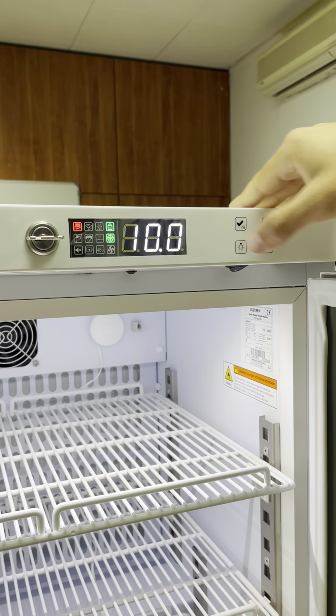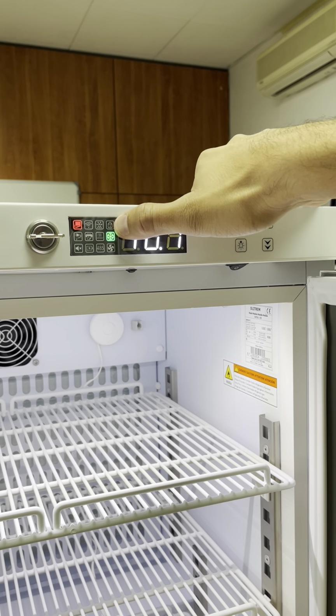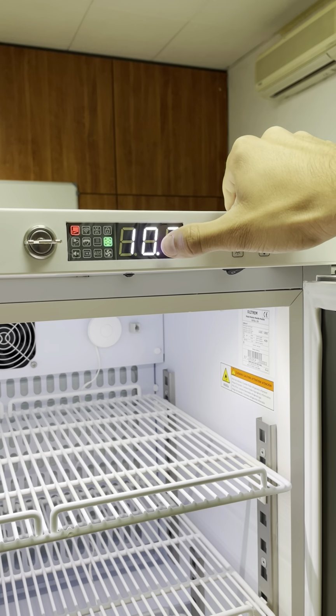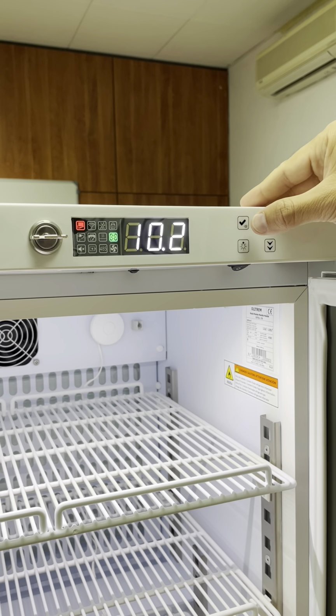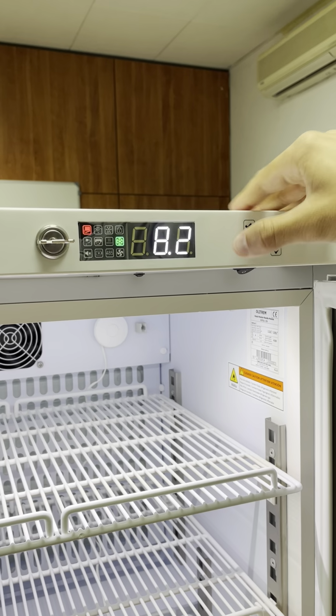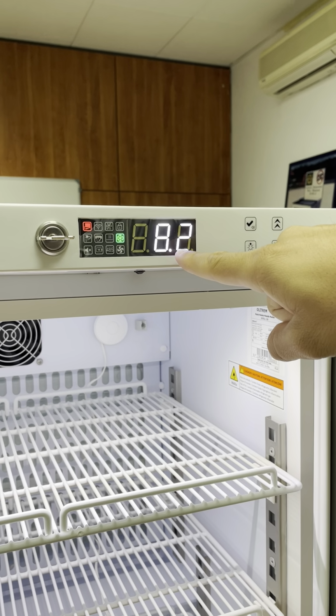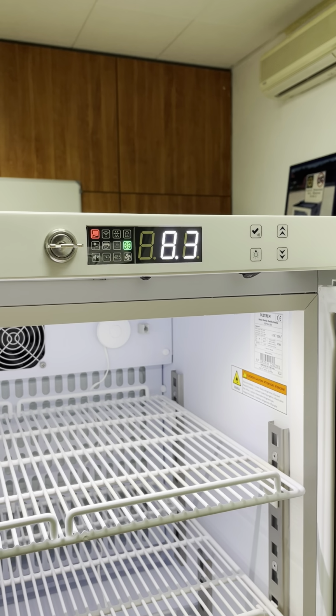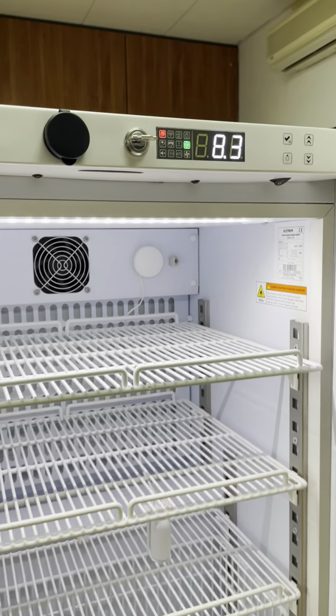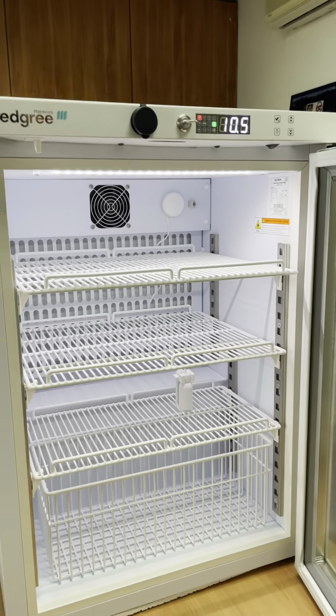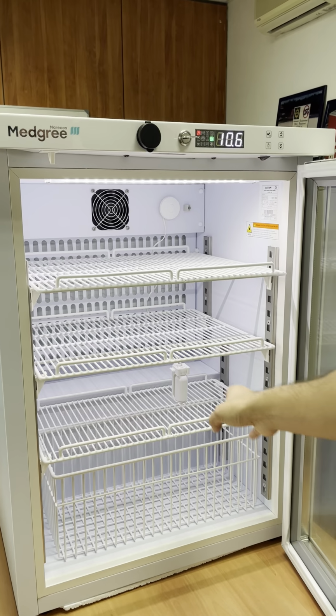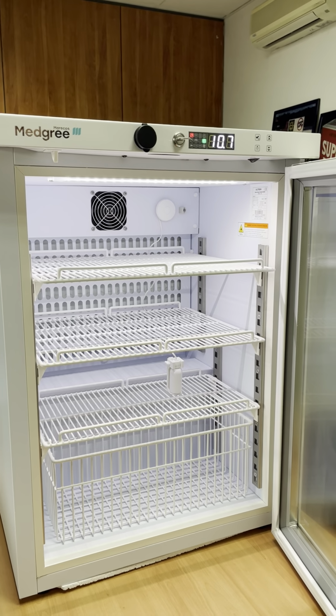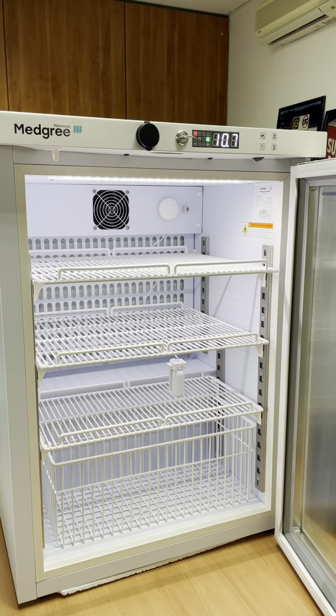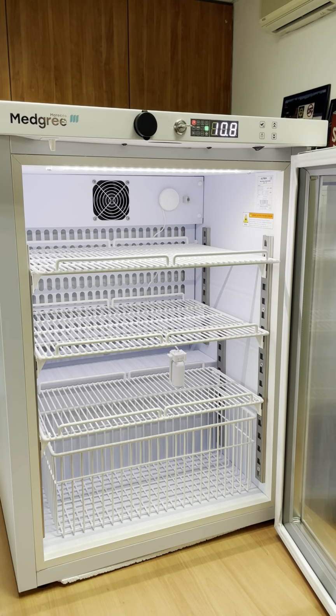In this case, I need to unblock it first. I unlocked it. Then if I touch it, 10.2 is the temperature of the air. If I click to see the second probe, I see the second probe is 8.2 or 8.3, meaning that the temperature of the air goes up very quickly when you compare it with the product probe. So that probe is more accurate when you need to know exactly what is happening with the medicines.